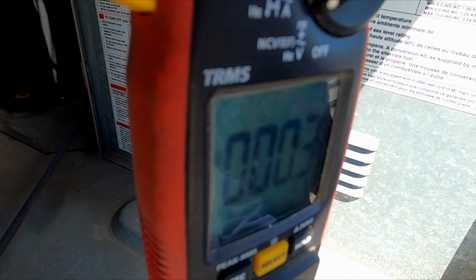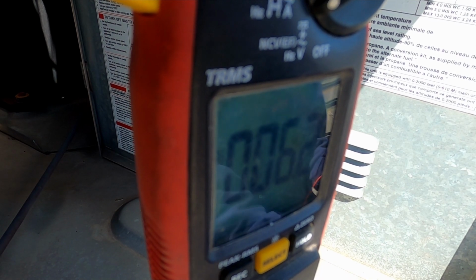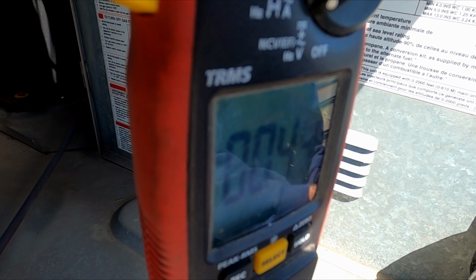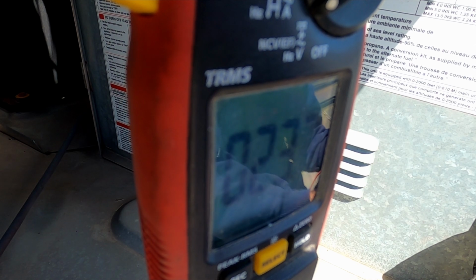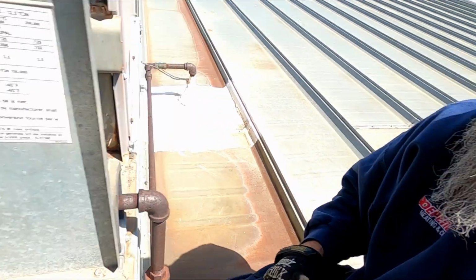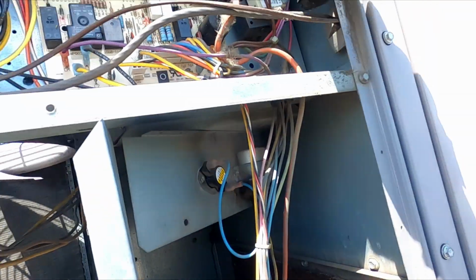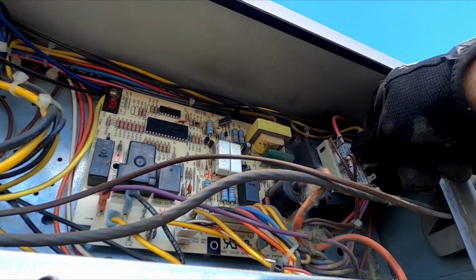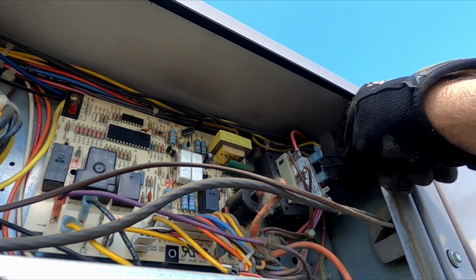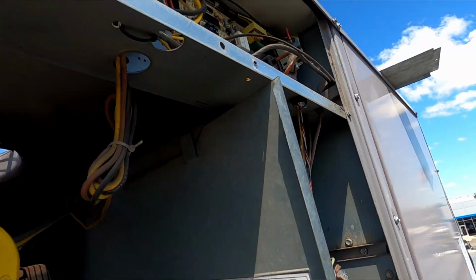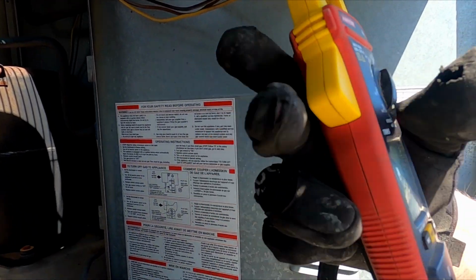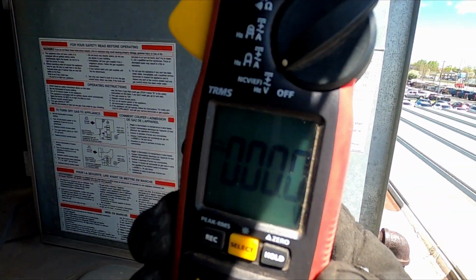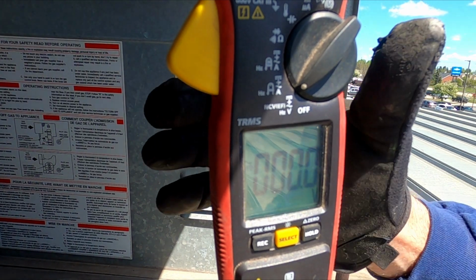So I'm tapped wrong. Now if I go to the gas valve, I got 23.7 volts. So 213, that's closer to 208. So I'm going to tap her on the 208 right there, and that should change my voltage on my gas valve—I should get 25 volts then. I don't know if you guys can see that.